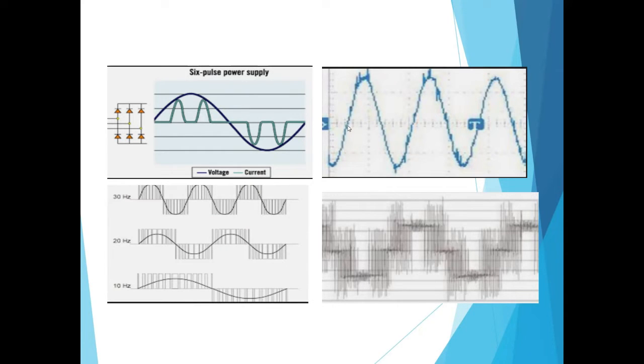And there are some back checks you can do that will help the longevity of not only the inverter, but also the motor. So you can see here that if it's at 30 cycles, meaning 30 cycles a second, it'll take that 4-pole machine at 60 hertz power and make it run at about half the speed. So we're controlling it, and you can go down to even 10 hertz. You can see the pulses. The one line here is the current waveform, and the other is the voltage waveform.